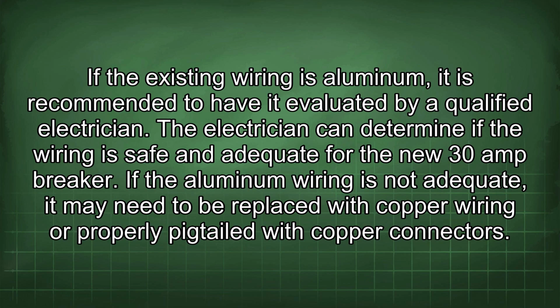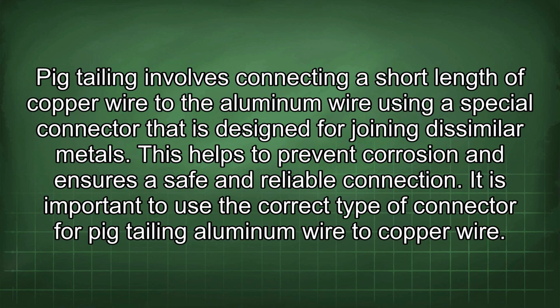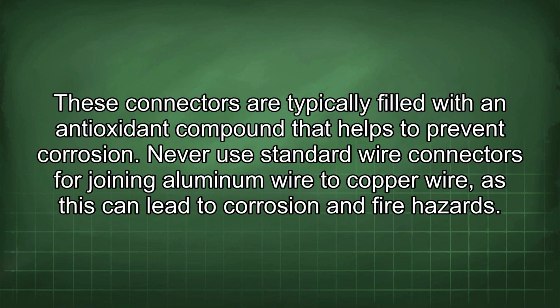If the aluminum wiring is not adequate, it may need to be replaced with copper wiring or properly pigtailed with copper connectors. Pigtailing involves connecting a short length of copper wire to the aluminum wire using a special connector that is designed for joining dissimilar metals. This helps to prevent corrosion and ensures a safe and reliable connection. It is important to use the correct type of connector for pigtailing aluminum wire to copper wire. These connectors are typically filled with an antioxidant compound that helps to prevent corrosion. Never use standard wire connectors for joining aluminum wire to copper wire, as this can lead to corrosion and fire hazards.